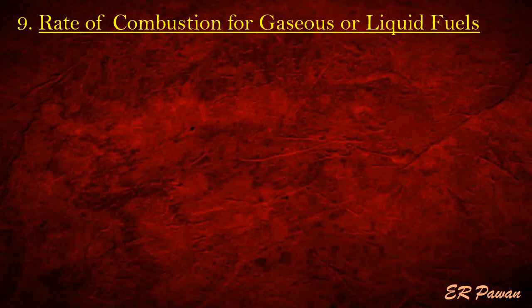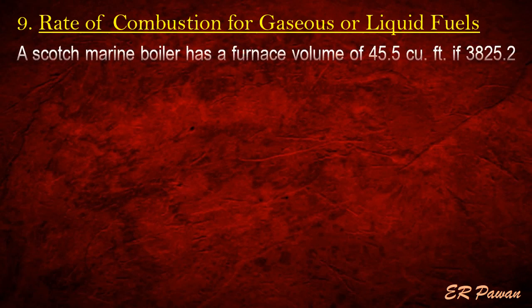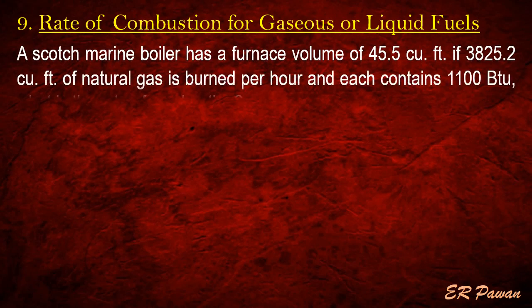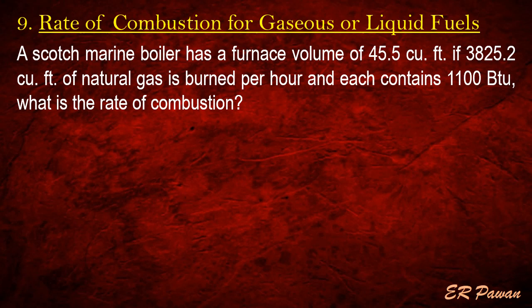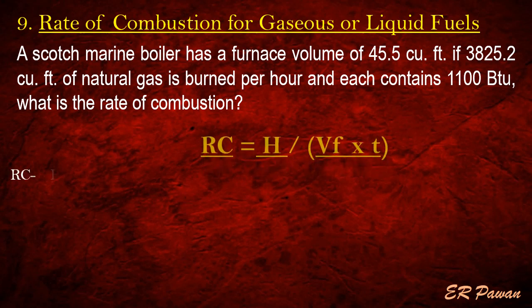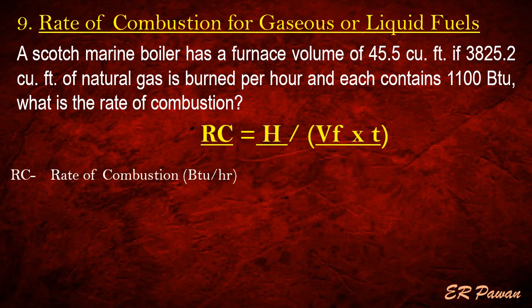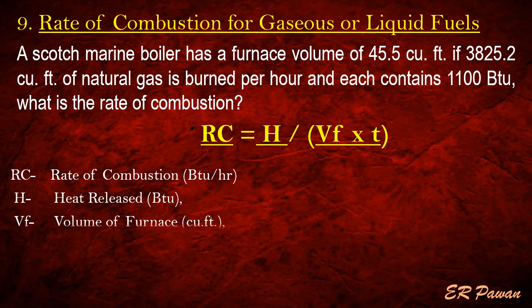Formula 9 — Rate of Combustion for Gaseous or Liquid Fuels. A scotch marine boiler has a furnace volume of 45.5 cubic feet. If 3,825.2 cubic feet of natural gas is burned per hour and each cubic foot contains 1,100 BTUs, what is the rate of combustion? Rate of combustion equals heat release divided by volume of furnace multiplied by time. Let's put the value in the formula.